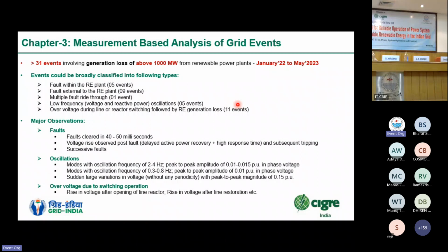Then we have been observing low frequency oscillations in voltage and reactive power. In these events, there have also been some specific cases where large voltage dips with no specific or periodic frequency were observed, and that has also resulted in generation loss in a few cases. And then there is overvoltage upon switching off any equipment like a reactor or restoration of a line, especially during peak solar hours. This has resulted in overvoltage and ultimately the tripping of the plants because of this high voltage.